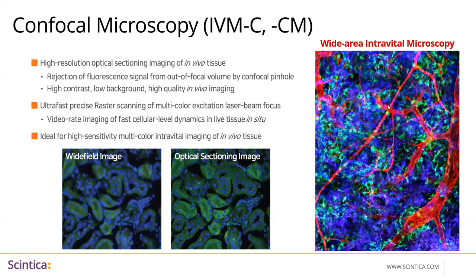I'm going to remind you about these microscopy techniques — what is confocal and what is two-photon — for those without background experience. Confocal microscopy is an optical imaging technique that uses a pinhole to block out-of-focus light coming from the background tissue, so it increases optical resolution and the contrast of acquired images. It offers the capability to optically section the tissue as you go deep, which is why it gives you high resolution.